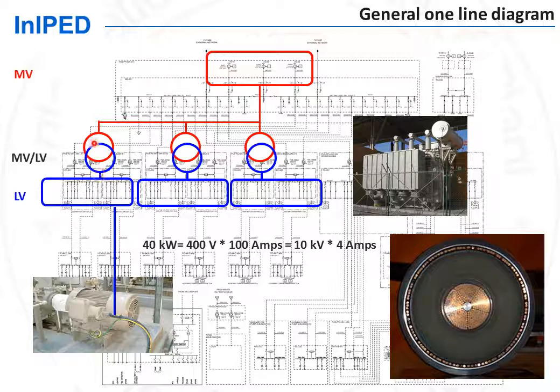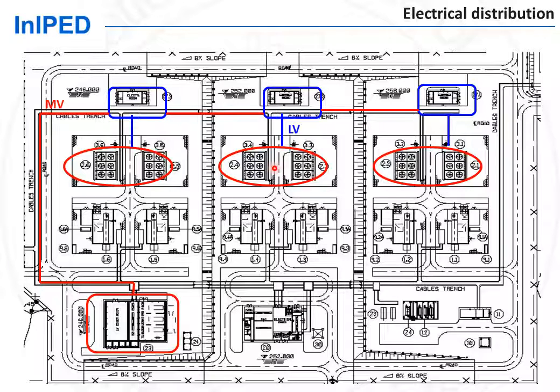Electric power is carried by medium voltage cables, like 10 kV cables, over a long distance. Therefore, electrical substations with transformers are located throughout the plant. Large power consumers are identified on the plot plan — for instance, here the large power consumers are the air-cooled heat exchangers. Electrical substations are located next to these high power consumers so that the length of the low voltage cables is minimized.